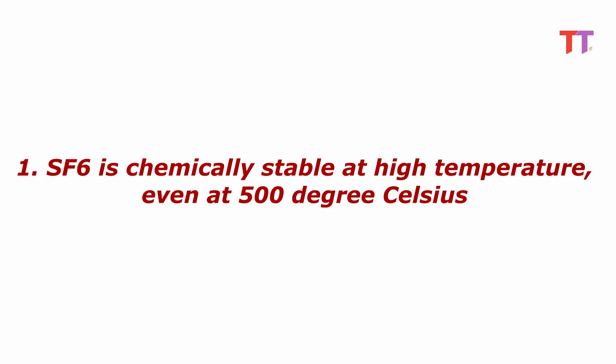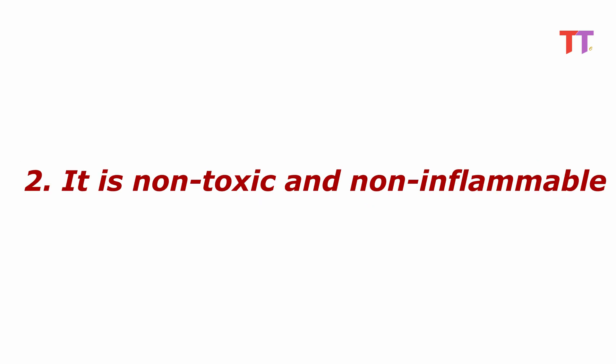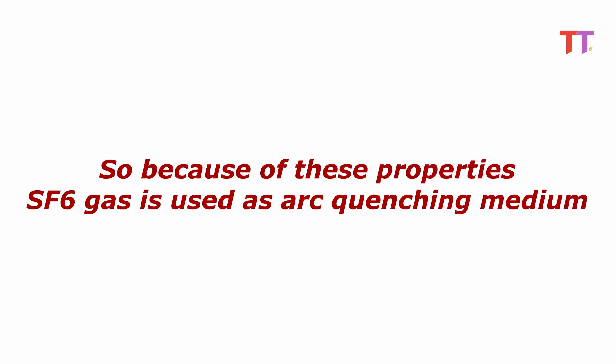SF6 is chemically stable at high temperature, even at 500 degrees Celsius. It is non-toxic and non-inflammable. It has excellent dielectric property, hence it is an outstanding arc quenching medium. So because of these properties SF6 gas is used as arc quenching medium.